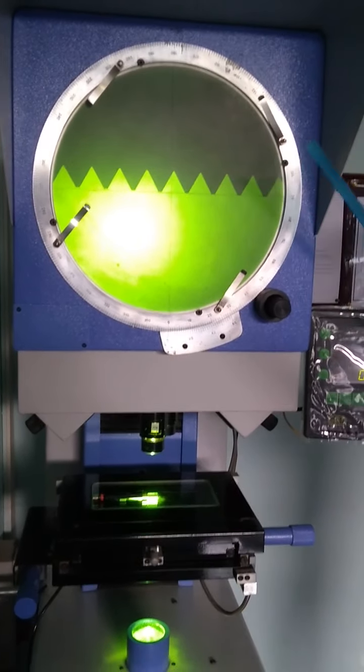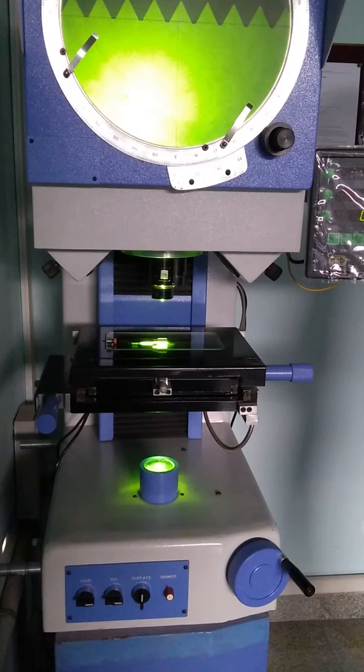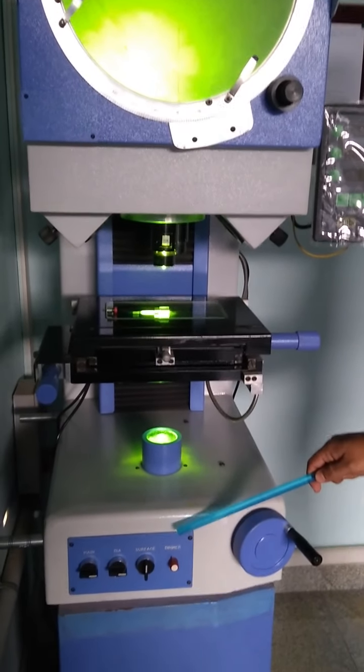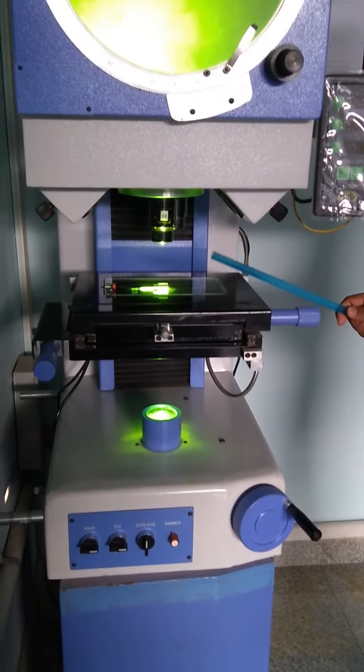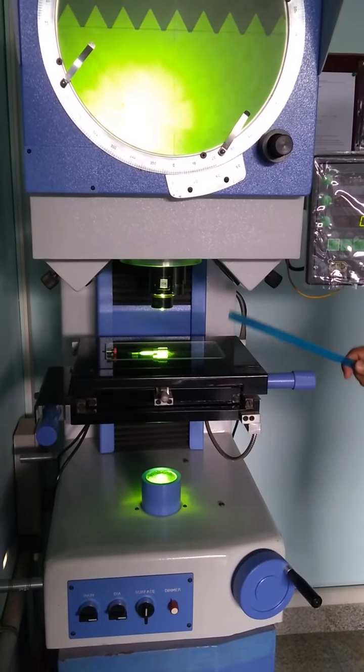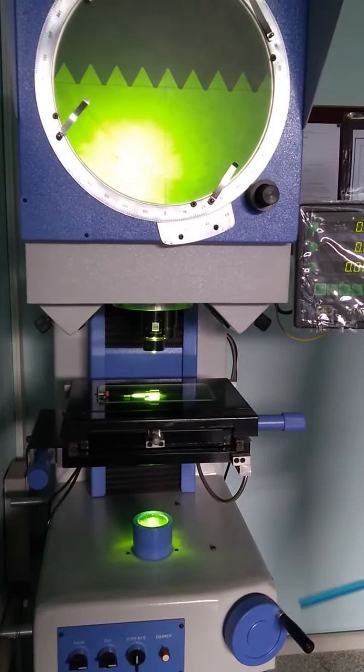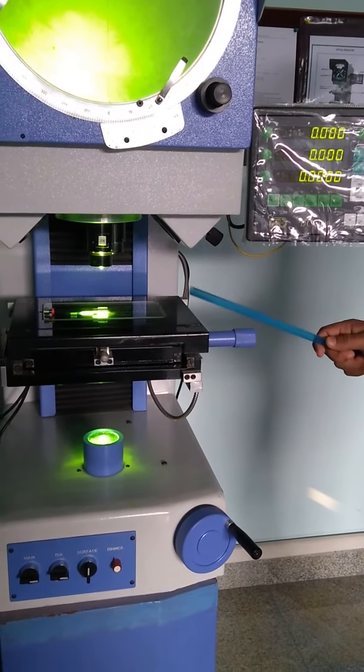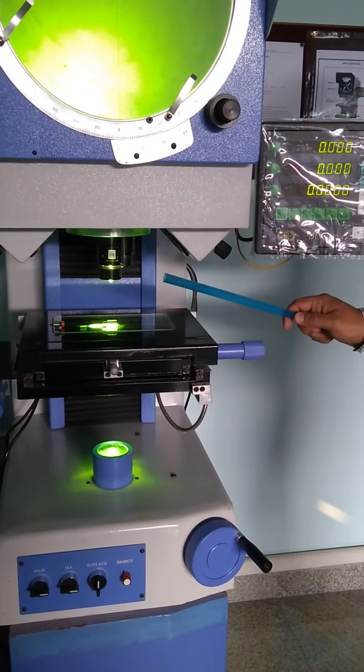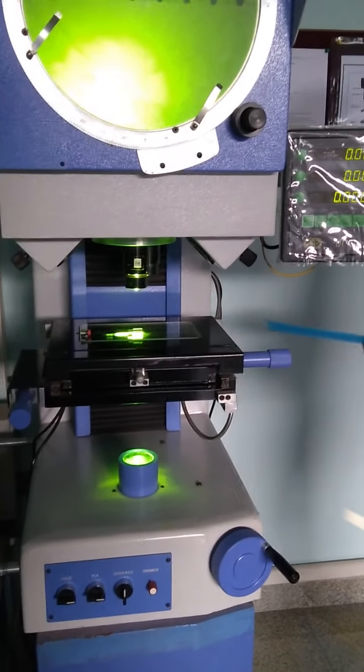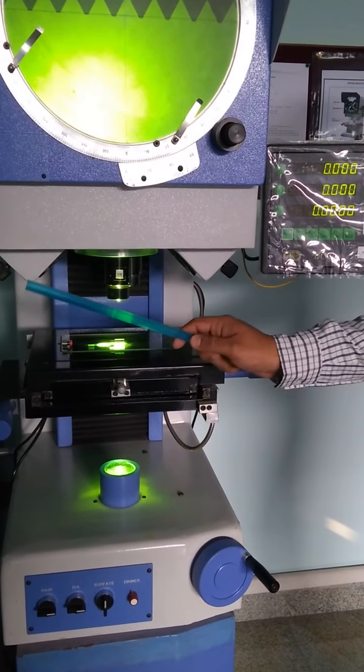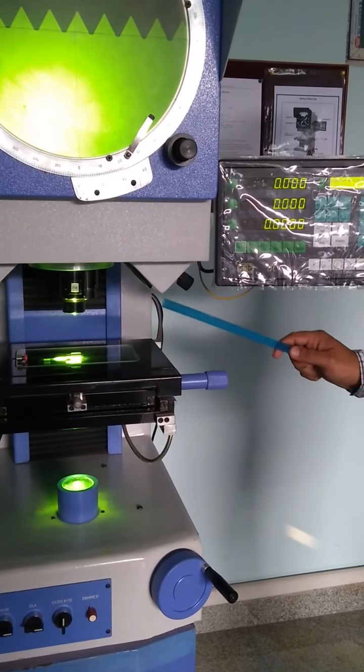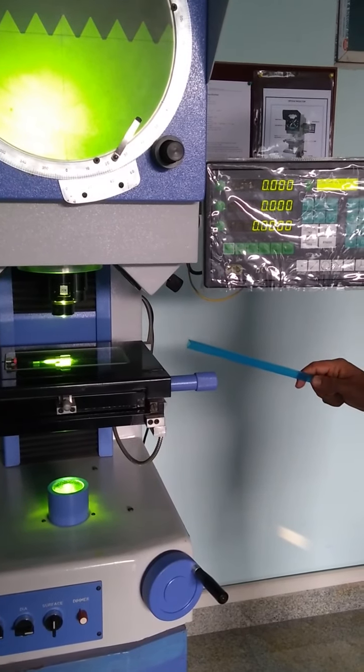Measuring of the sample can be done on projected screen. Now we will understand the important parts of this profile projector. The first and foremost is the supply control units which is used to regulate the amount of incident light on the specimen to reflect it back on the screen. Then there is an elevating screw here which can be operated to rise or lower the platform. The platform is equipped with vertical movement as well as horizontal movement. The vertical movement is enabled to find out the major diameter, minor diameter and depth of the thread, whereas the horizontal movement of the platform can be done to find the pitch of the given thread.